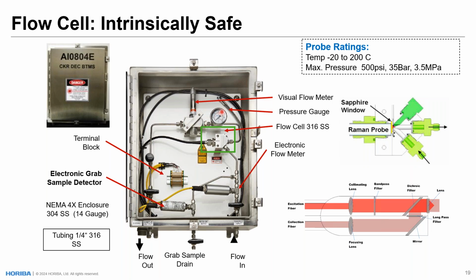Likewise, our various flow meters and pressure gauges inside the flow cell enclosure ensure that the sample is flowing through the cell at your desired and constant rate. So an easy check to make sure that your stuff is going through the way that you would expect it to. Also, the tubing that we put in here is extremely straightforward. It goes in, goes through, and then comes out. We try to make it as simple as possible so that the long-term durability of the flow cell is increased by the lower amount of tubing that is used. And depending on the corrosiveness of your sample, and also the various standards that may be used in different industries and applications, we can modify the actual material that is used in this tubing here with our Swagelok.